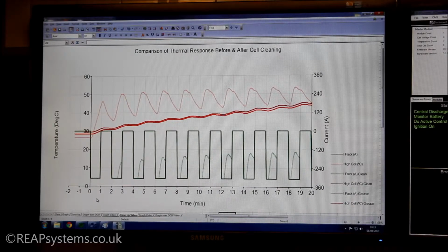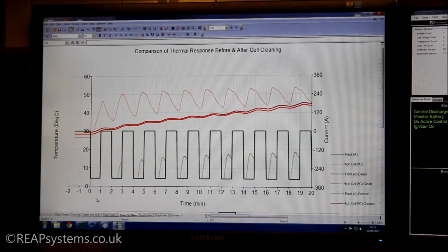And there's very little difference between the behaviour for both of those. So what are these two, greased and cleaned and greased, and just cleaned, right? That's right. And there's not a big difference, which means no harm in greasing your contacts if you're using the right sort of products, and that should preserve the metal from oxidation. So what are the remaining discharge bursts looking like?